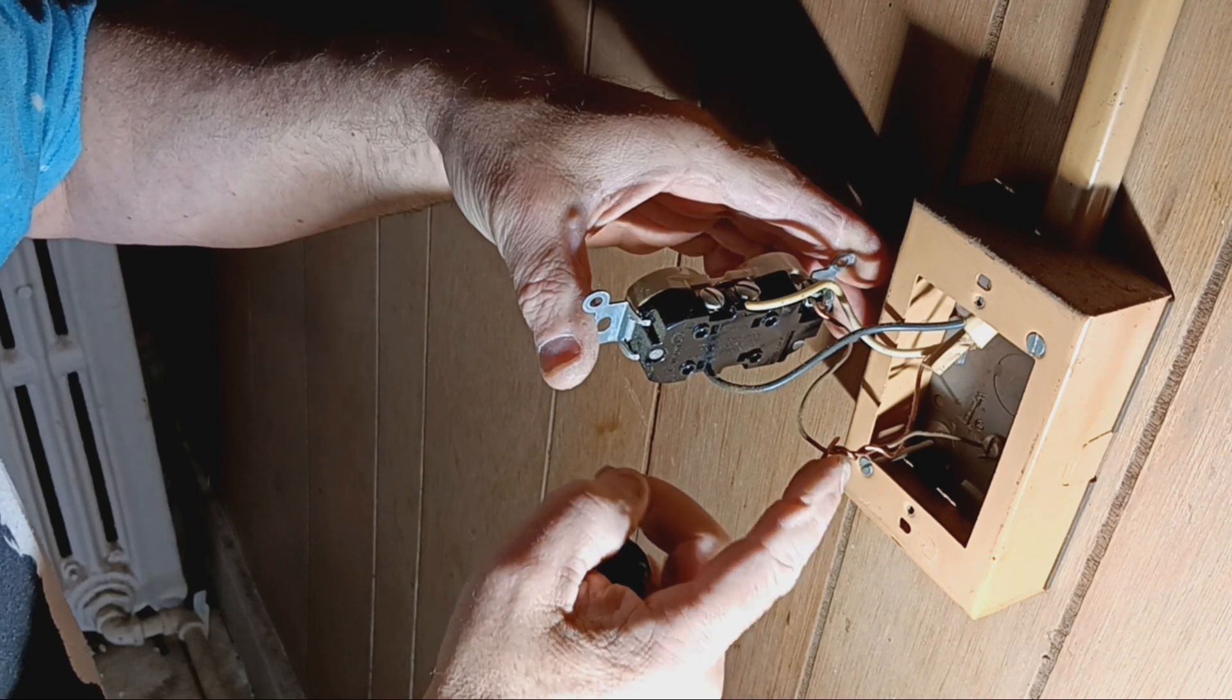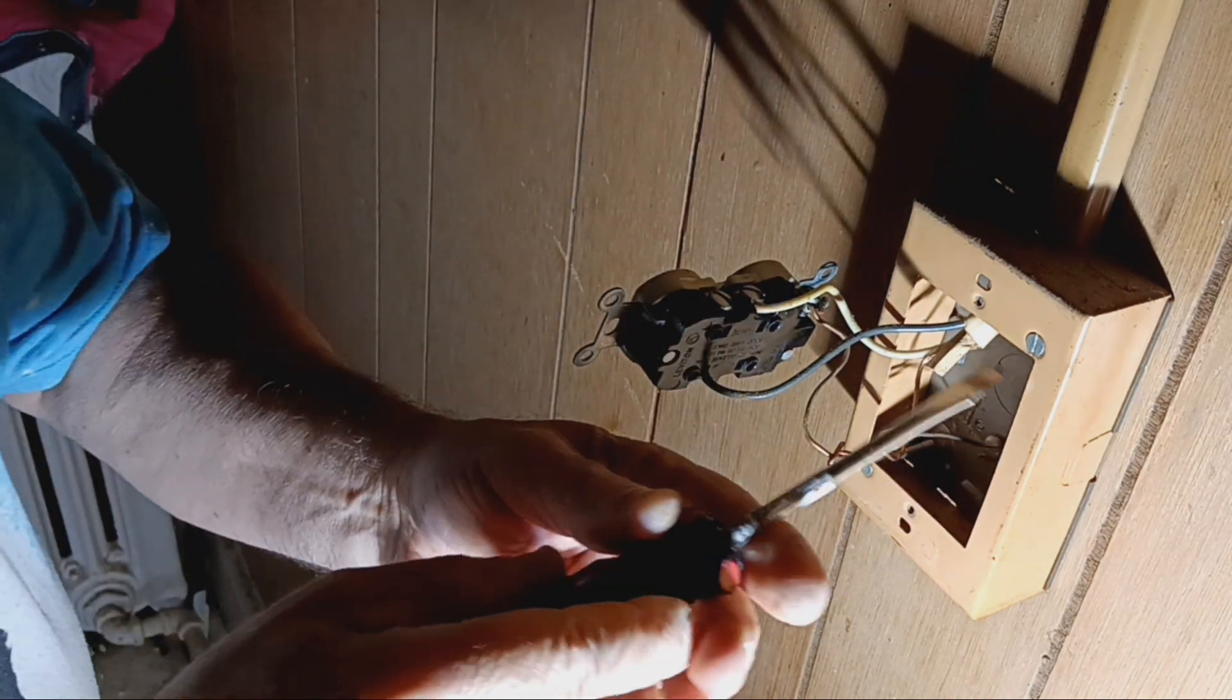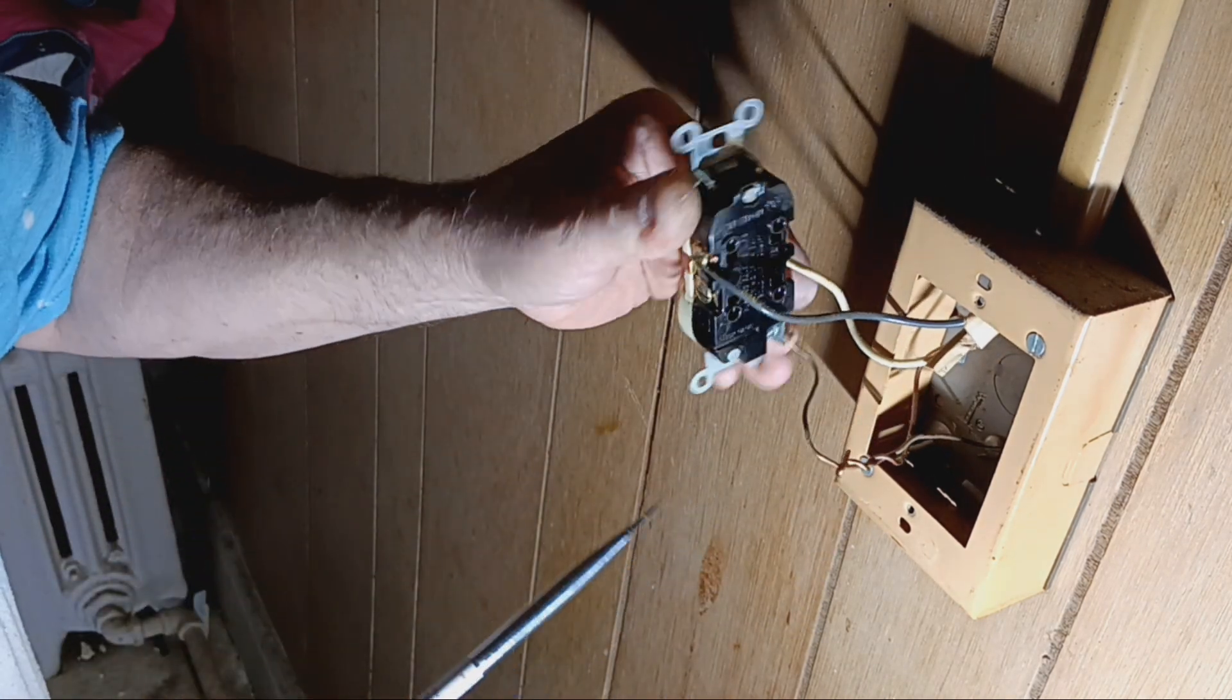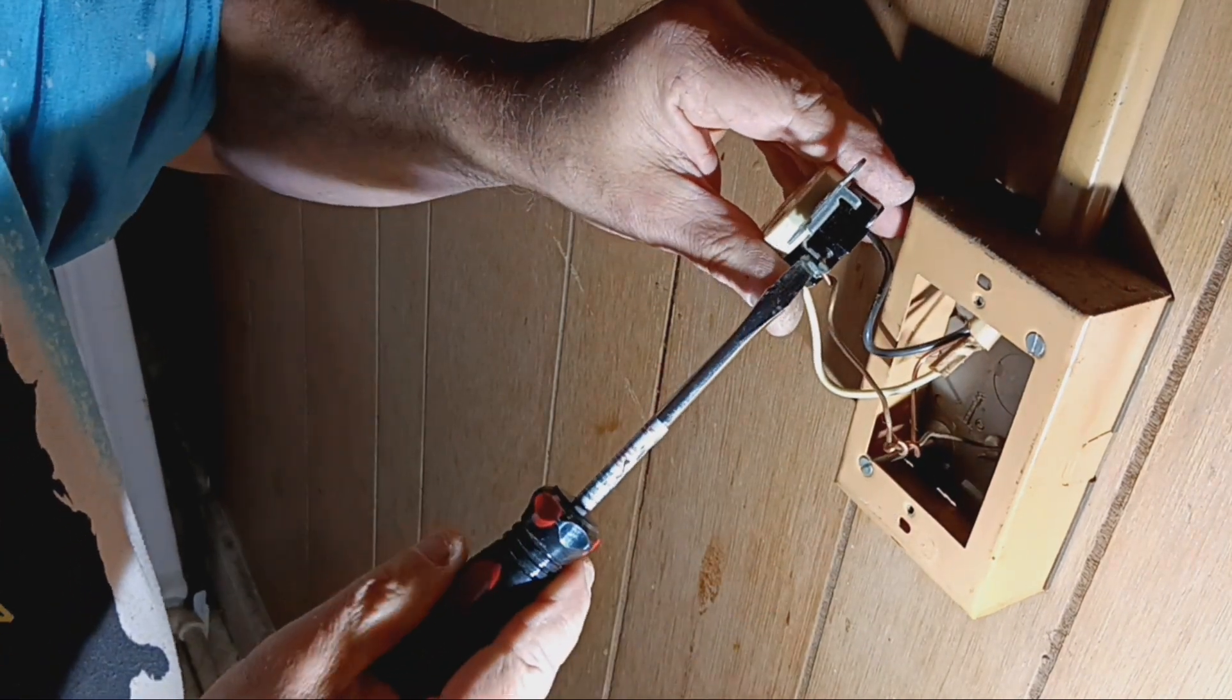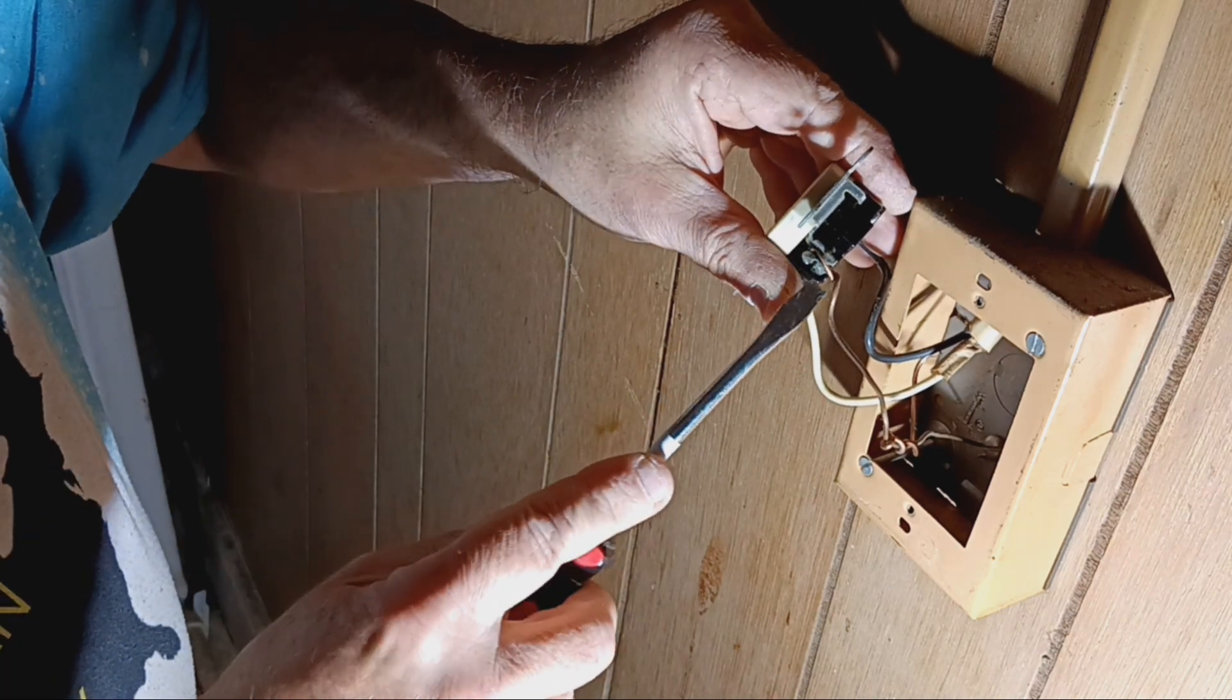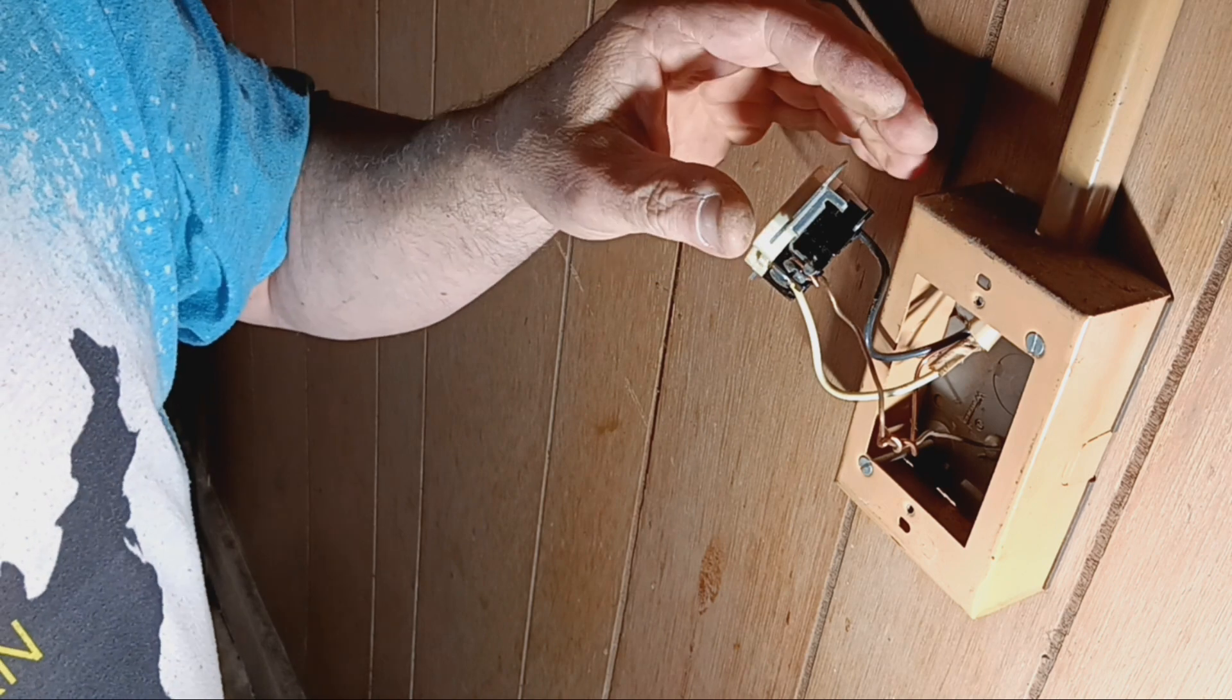It's just right up close. The only thing is they didn't put a crimp sleeve or a wire nut where the ground goes to the green screw in the back of the box. So we're going to undo this ground wire here and we're going to put a crimp sleeve in here to bring this up to code. That green screw wasn't even very tight, so we will open this up.